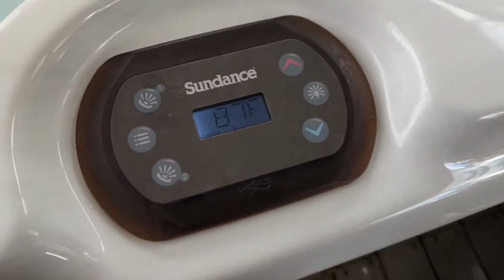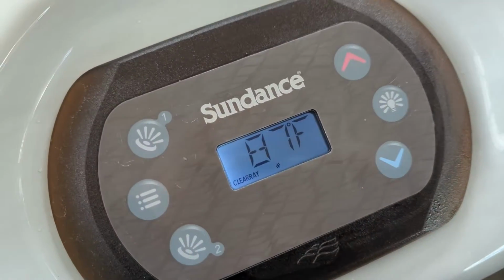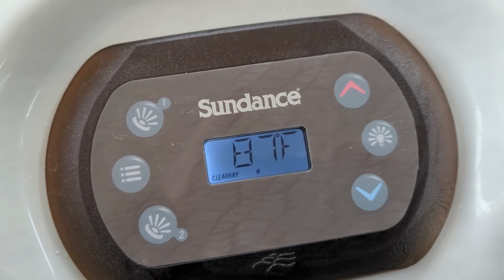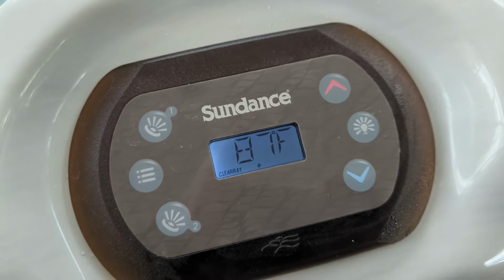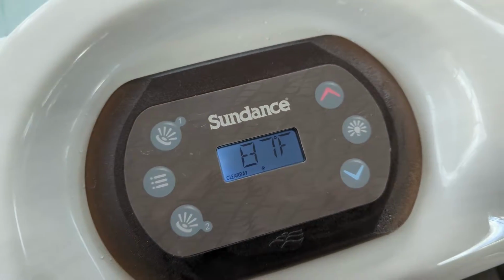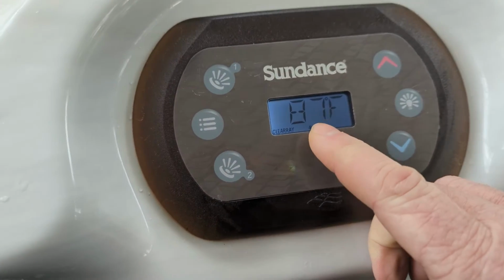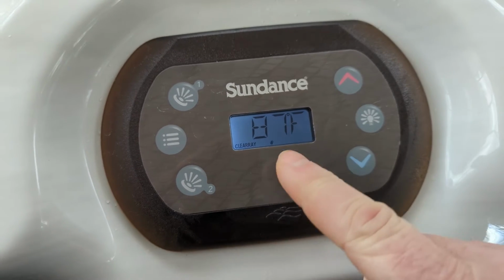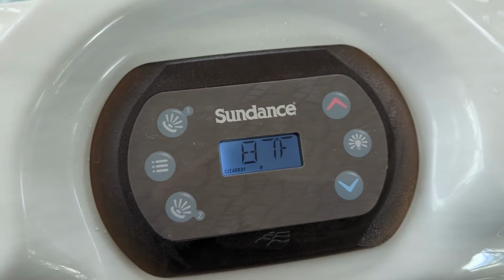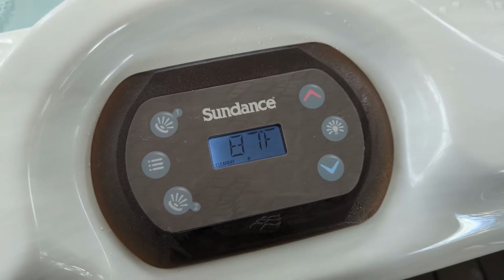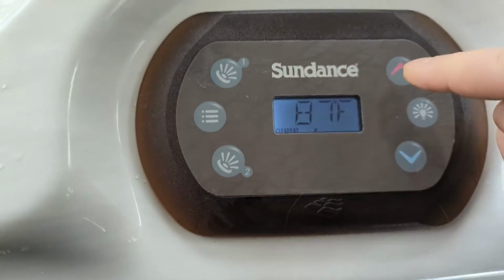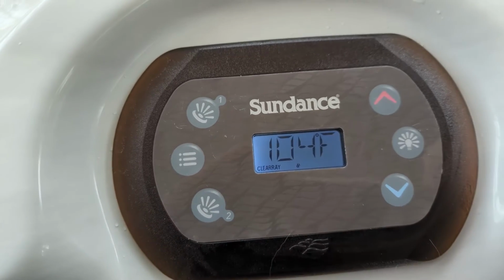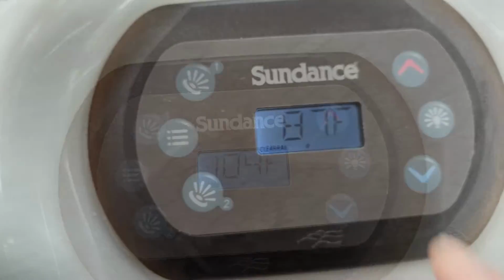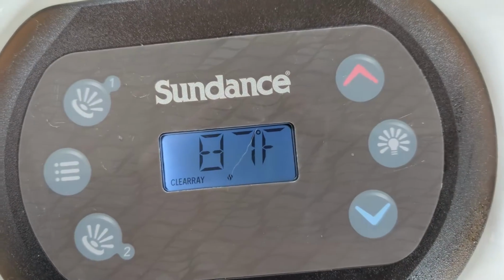Here we have a Sundance hot tub that's not heating up. It says 87, but that's not from the heater at all, it's from the motor heat. Whenever you see a temperature in the 80s, like 85 or 88, it's normally just the heat from the pumps still running. It's just not heating up to 104. It's set to 104, it just won't go past that, and there's no error codes or anything like that.